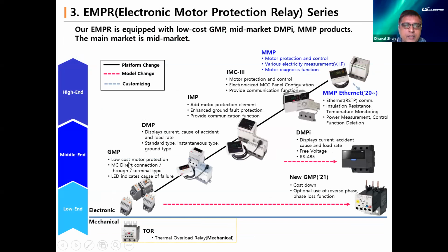Moving ahead, conventional relay versus our EMPR. We have shown the ladder as per the platform available for the various relays. GMP is the low-cost motor protection relay, as Rajesh mentioned earlier. It is an economical relay wherein you get current protection, and it can be mounted directly on the contactor. Being an electronic overload relay, you can always have type 2 coordination, absolutely no problem with these overload relays. The second product is DMP, which in addition to current also monitors the cause of the trip. It is available in standard type, instantaneous type, and ground type.